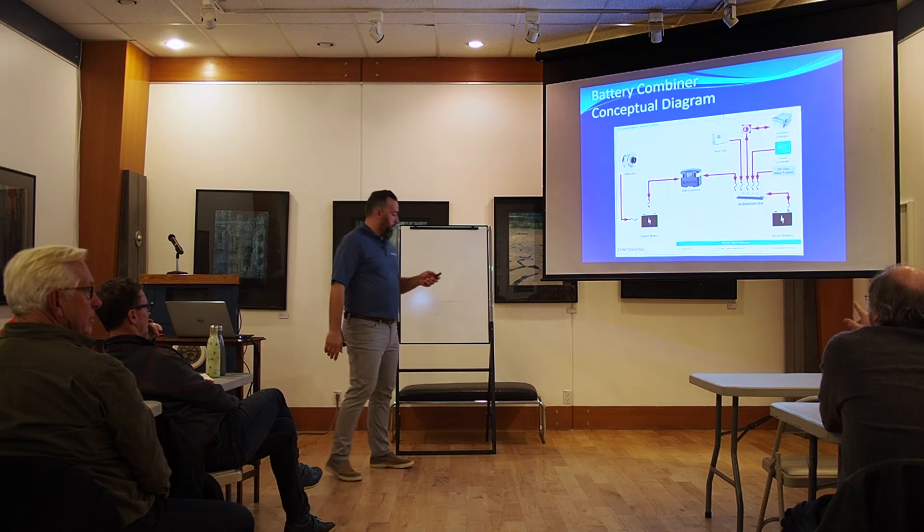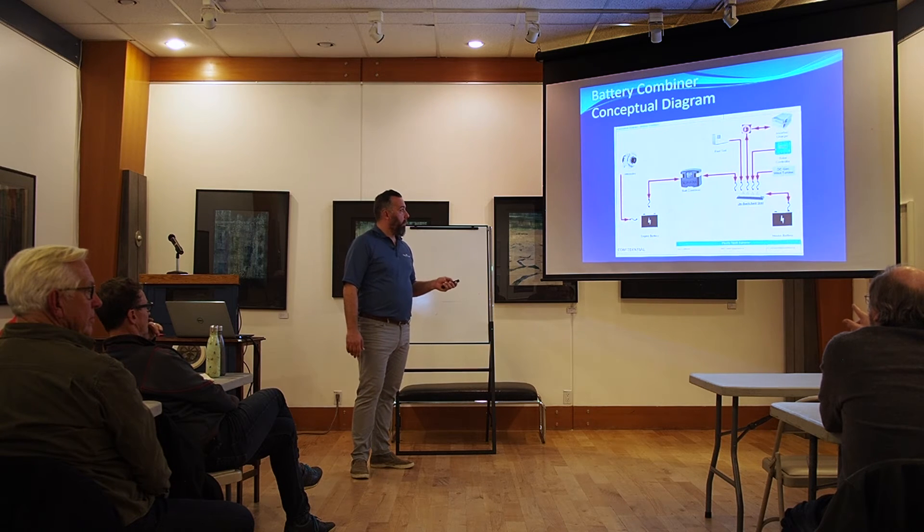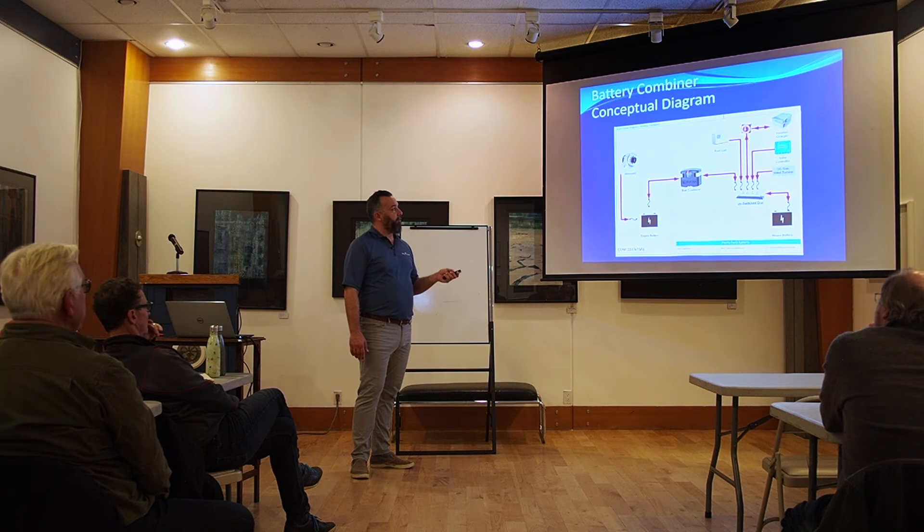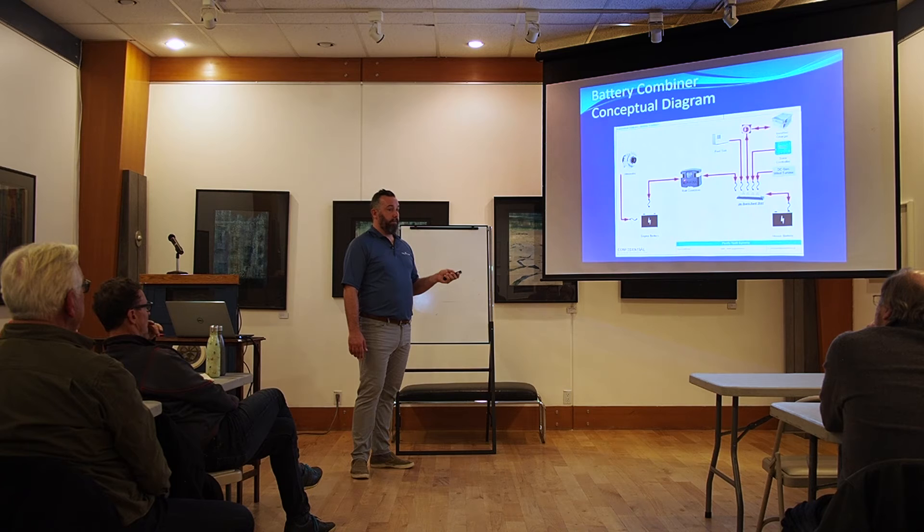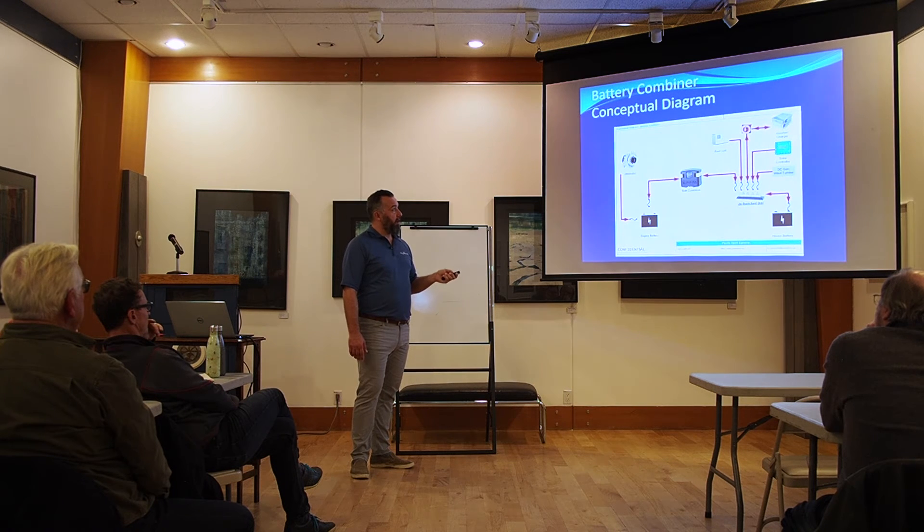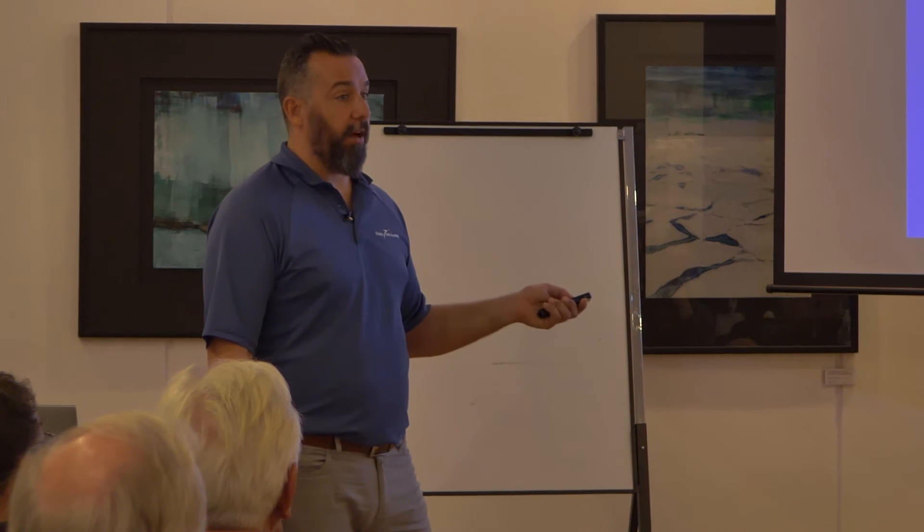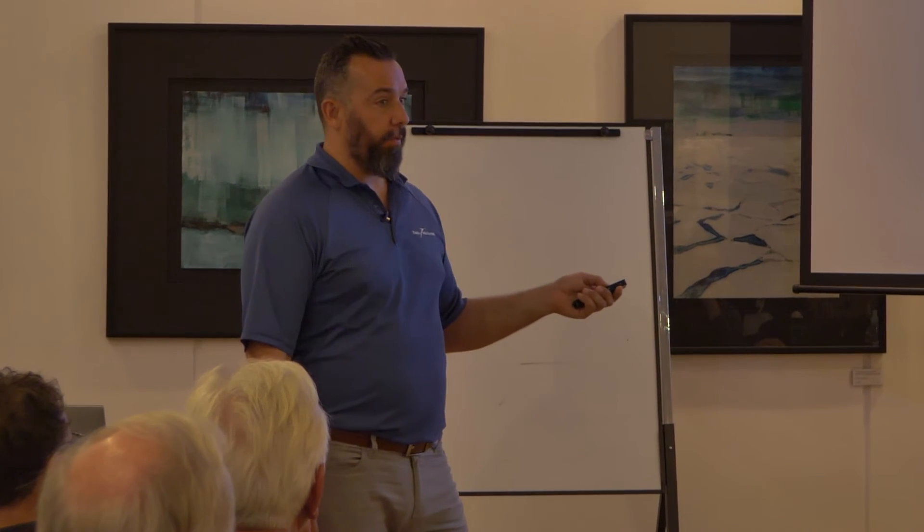Question? If your fuses are blowing, can't you just use bigger fuses, bigger wires? Well, the problem is this is rated for a maximum ampacity. You could, but this is a 120-amp device. So if you're using too big a fuse, then you need to change that combiner. That combiner then goes up to 300 amps.